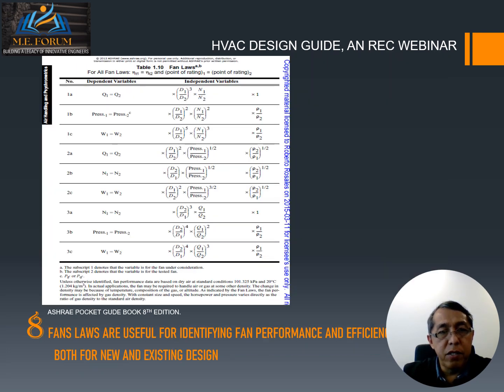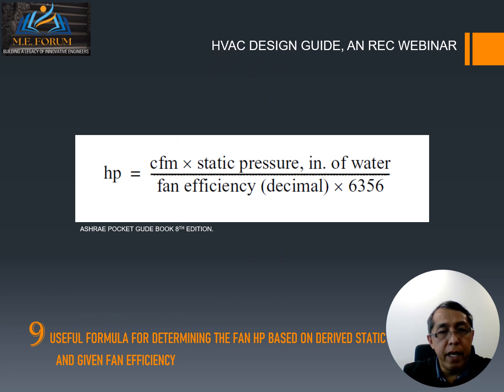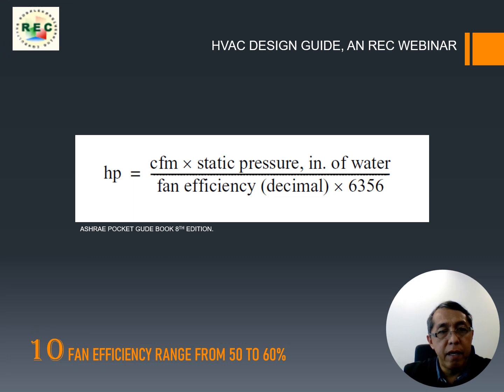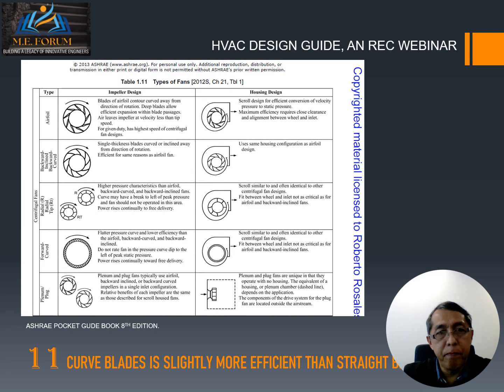Number 8, fan laws are useful for identifying fan performance and efficiency, both for new and existing design. Number 9, a useful formula for determining the fan horsepower based on derived static pressure and given fan efficiency. Number 10, fan efficiency ranges from 50 to 60%.